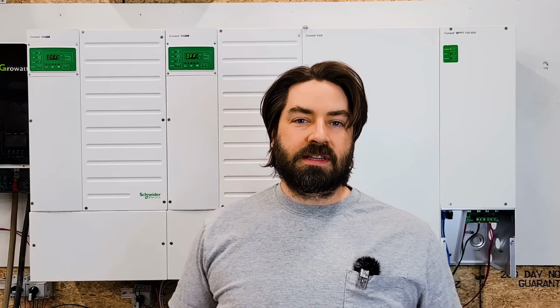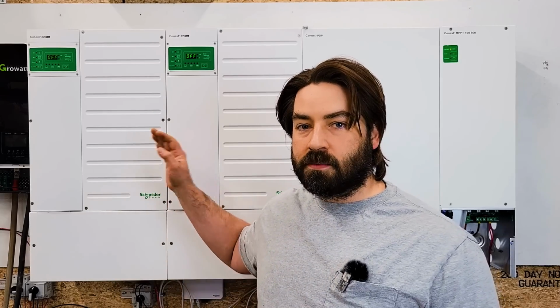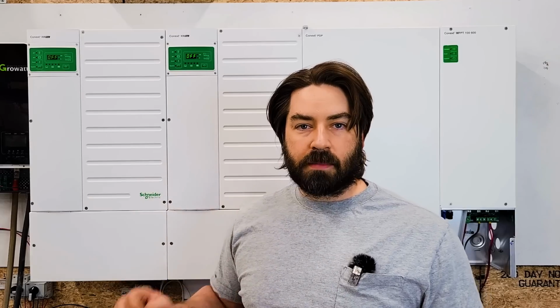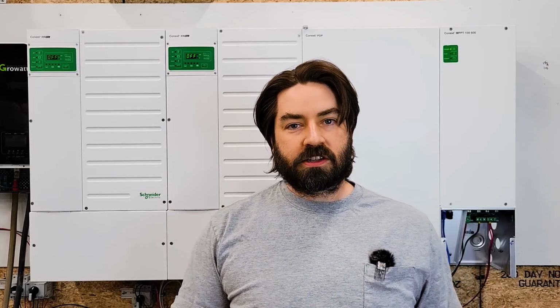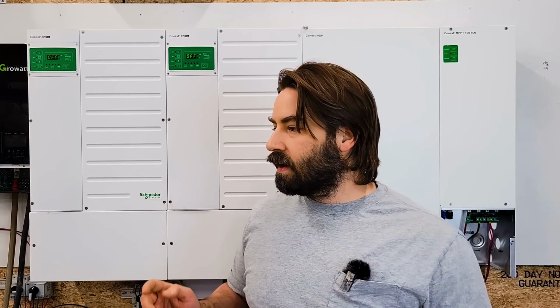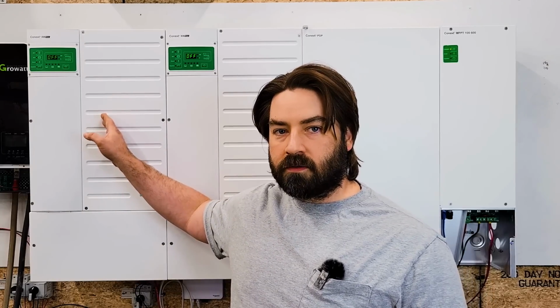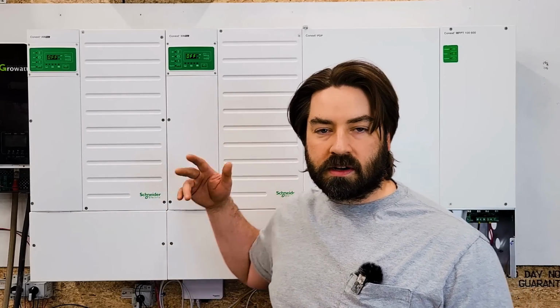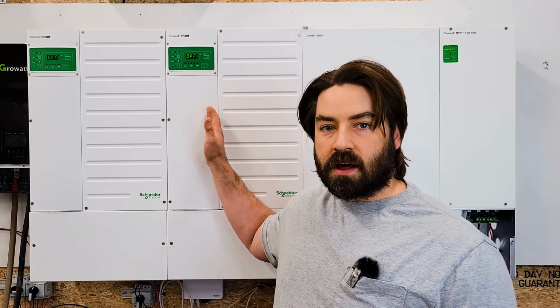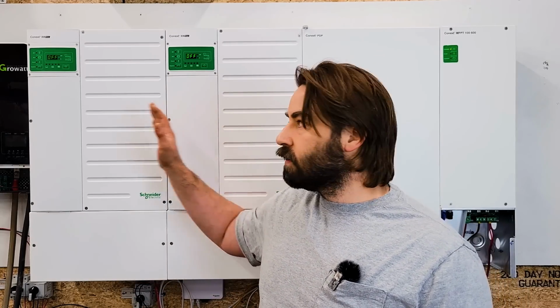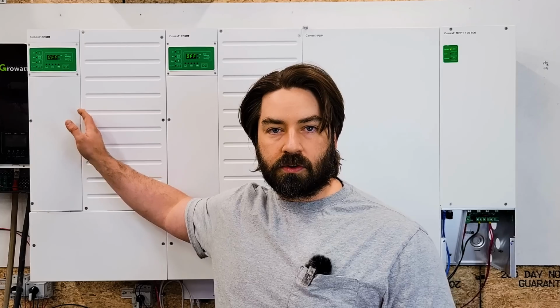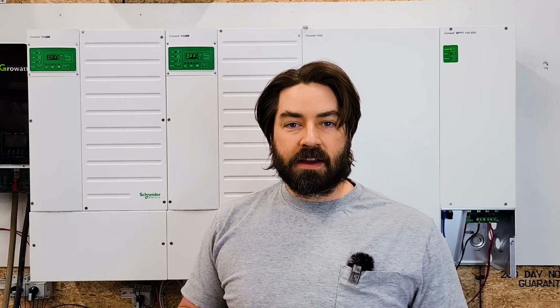And for some reason I missed it. It is printed in the manual, but you have to put everything into standby mode in order to change the device numbers. And I think maybe I was just putting this one inverter in standby mode, but I still had the other one in operation. But basically I had to set this one to device number 1 and this inverter to device number 2, so the master and the slave. And now they finally work.